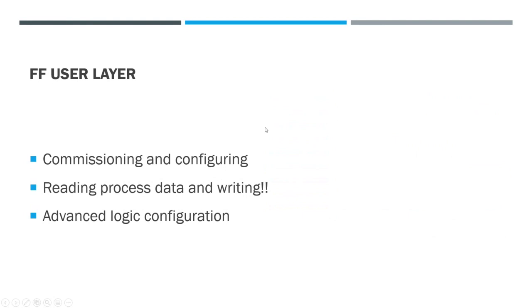User layer, what is it used for? It's the first time we've talked about the user layer. Things that go on inside it: provisions are made for commissioning and configuring, the reading and writing of process data is handled in there, and advanced logic configuration is handled inside the user layer. This is significant because when we talked about Foundation Fieldbus, we said it was capable of performing PID within the devices themselves. This is the provision in the user layer that allows that to occur. That's what we're talking about with advanced logic configuration.